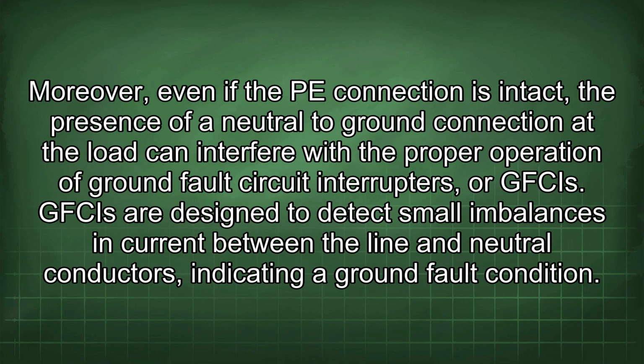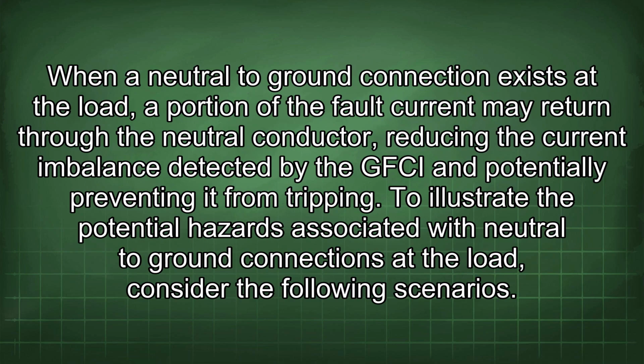Moreover, even if the PE connection is intact, the presence of a neutral to ground connection at the load can interfere with the proper operation of ground fault circuit interrupters, or GFCIs. GFCIs are designed to detect small imbalances in current between the line and neutral conductors, indicating a ground fault condition. When a neutral to ground connection exists at the load, a portion of the fault current may return through the neutral conductor, reducing the current imbalance detected by the GFCI and potentially preventing it from tripping.